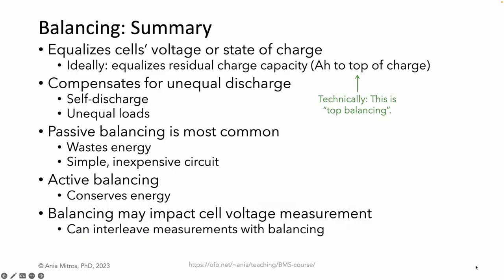Let's summarize what we've learned about balancing. Balancing equalizes the cell's voltage or state of charge. Ideally, it equalizes the cell's residual charge capacity, or the amp hours remaining to top of charge, which is technically called top balancing. Some systems balance to another point on the curve. Balancing compensates for unequal discharge or leakage, including cell self-discharge internal to the cells and unequal loads external to the cells. Passive balancing is most common.